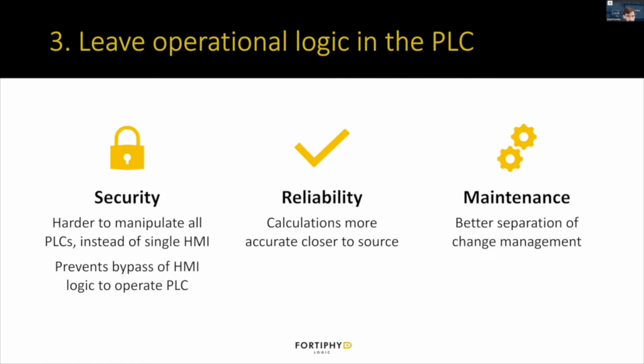The security benefits to this approach, again, are just making it harder for the attacker to manipulate things, especially if you have some kind of single centralized HMI talking to a bunch of different PLCs. If it was all in the HMI, that's only a single target that the attacker has to compromise. Whereas if the logic is spread out in the PLCs, the attacker has to compromise all the PLCs to really achieve some kind of physical impact to the process. And a lot of times the security and access control on the HMI itself is not great. So this prevents the attacker from just bypassing the HMI logic to operate the PLC, and the checks are actually happening on the PLC itself. They can't just send the Modbus command directly to the PLC to cause some problems.